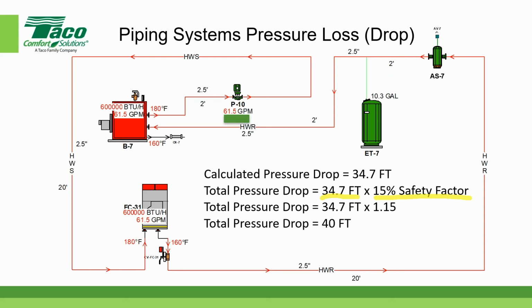And if you'll notice, the flow was always 61.5 gallons per minute. I tend to round things up. So when it came to the pump selection, I selected a pump at 65 gallons per minute at 40 feet. Ta-da! So that, in a nutshell, is how you do a manual calculation for pressure drop in a piping system. It doesn't matter, by the way, how complex the piping system is. The procedure that I've outlined here manually is exactly the same.